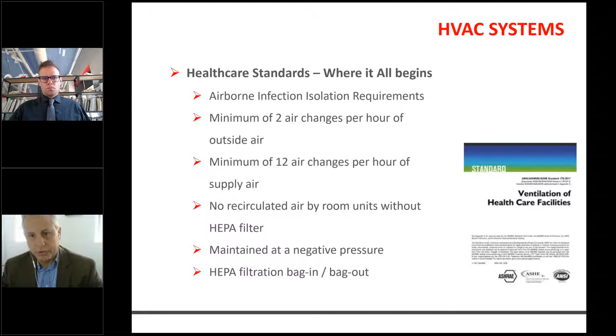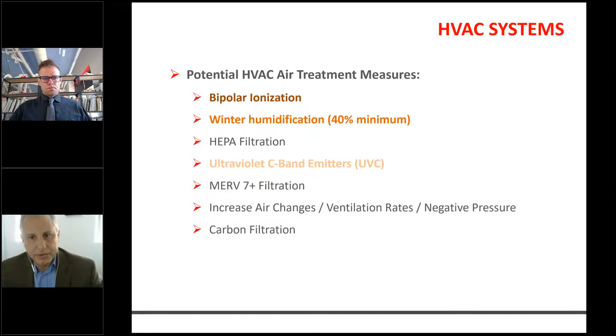I'm going to discuss some potential measures for treating air before it's applied to the building through the central HVAC system. I got these listed in descending order of effectiveness with respect to airborne pathogens, particularly viruses and coronaviruses. The ones I've highlighted tend to be best suited for retrofit applications. A couple things to look at is increasing your supply air changes and filtration. There's some challenges associated with that.